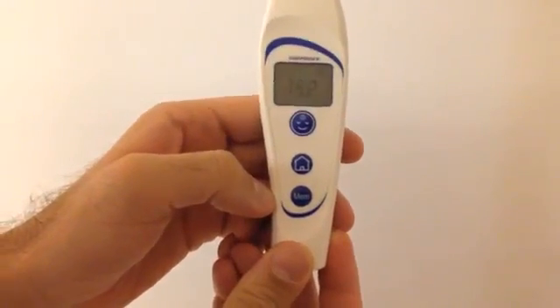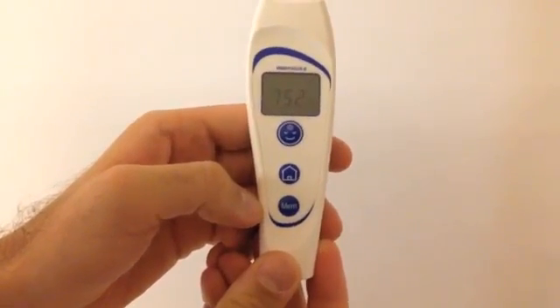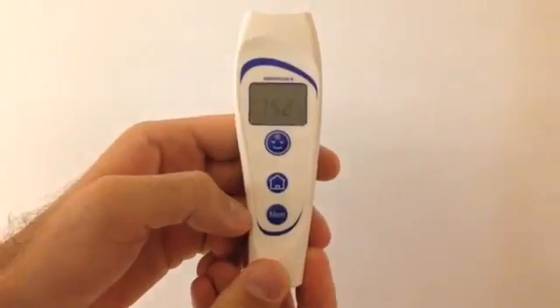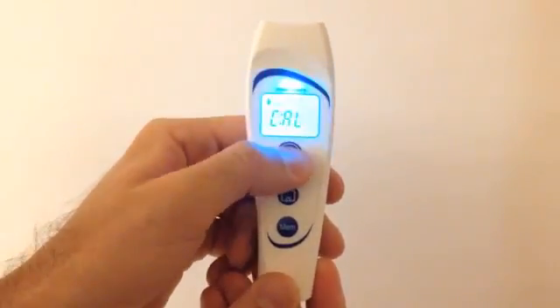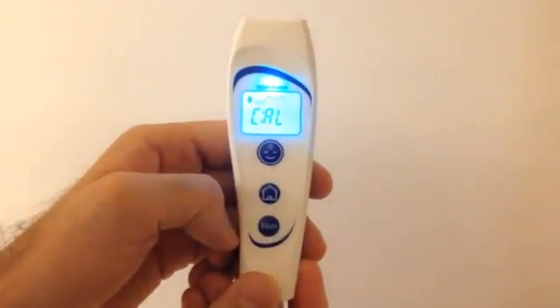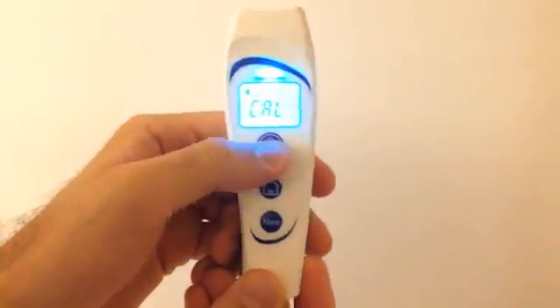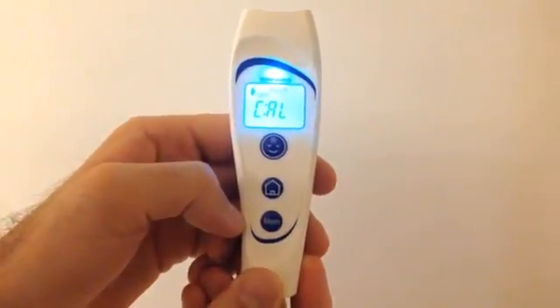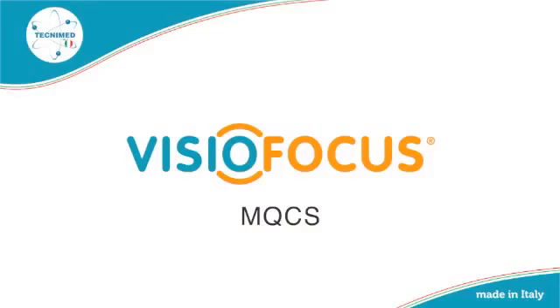Very important: the manual quick calibration system, MQCS, is mandatory. This means that if you don't calibrate, the device won't let you take any measurement, but it will suggest making the calibration. Proceed as follows.